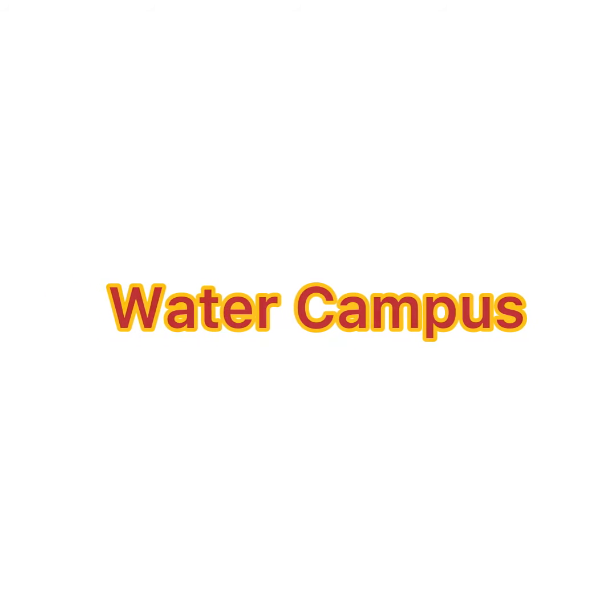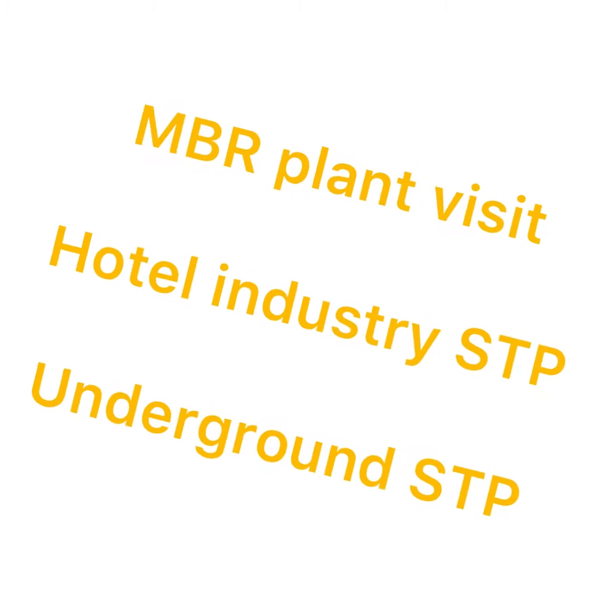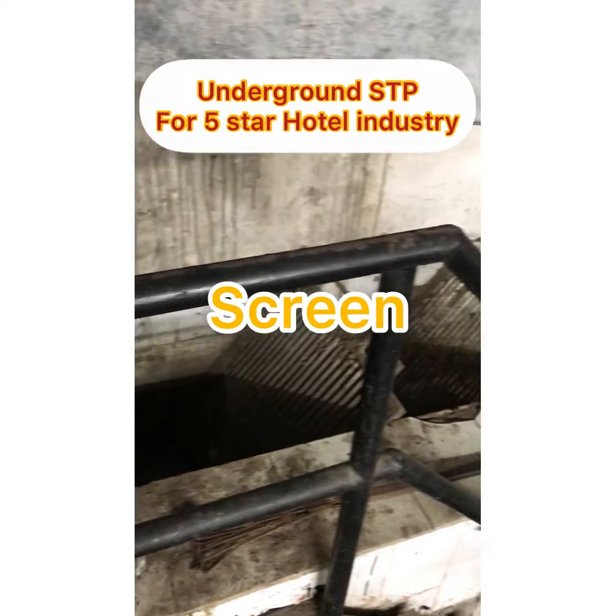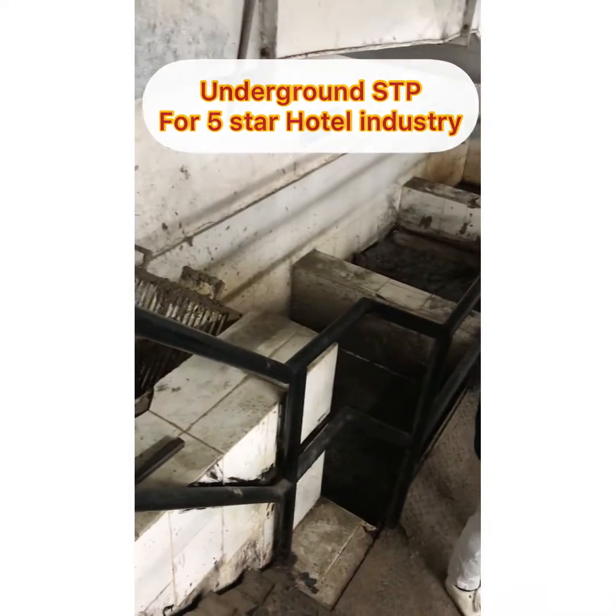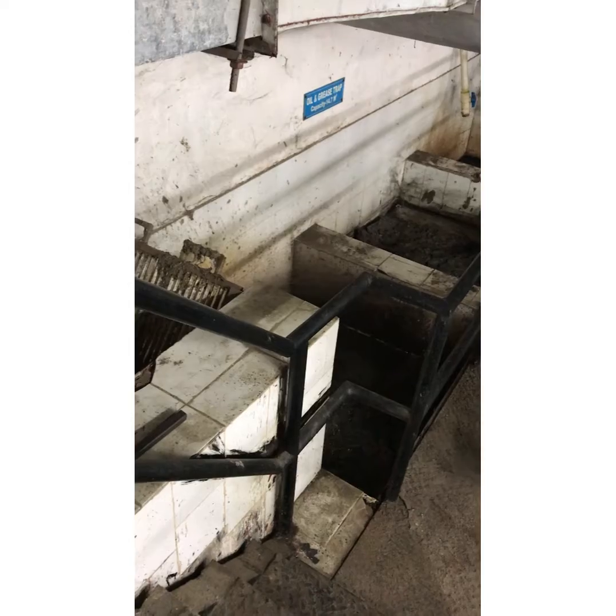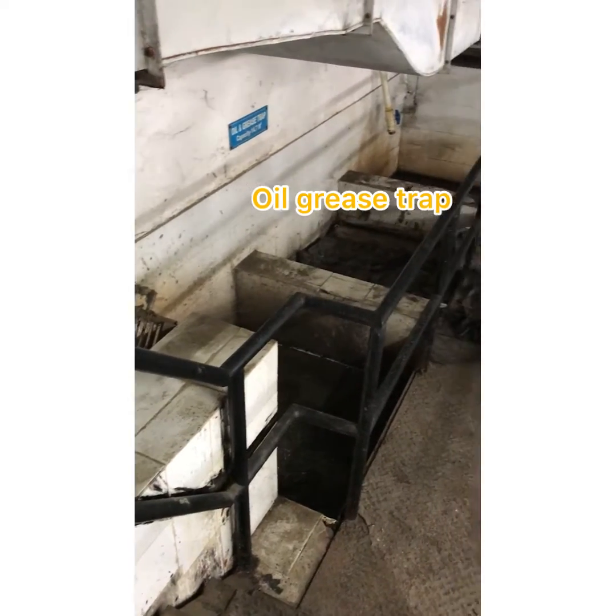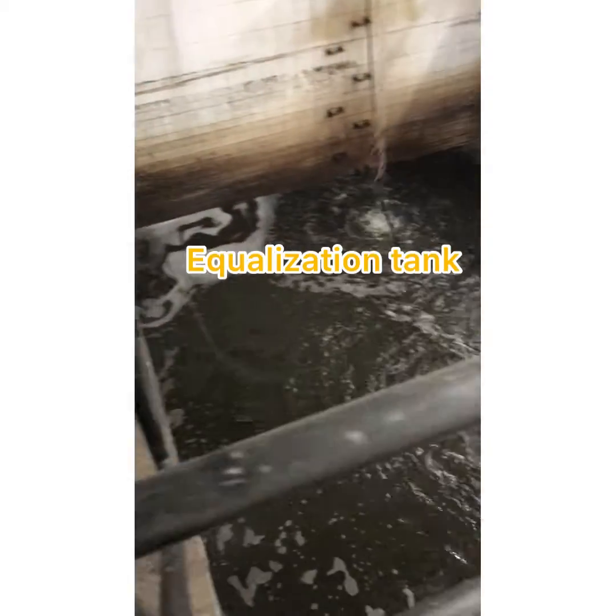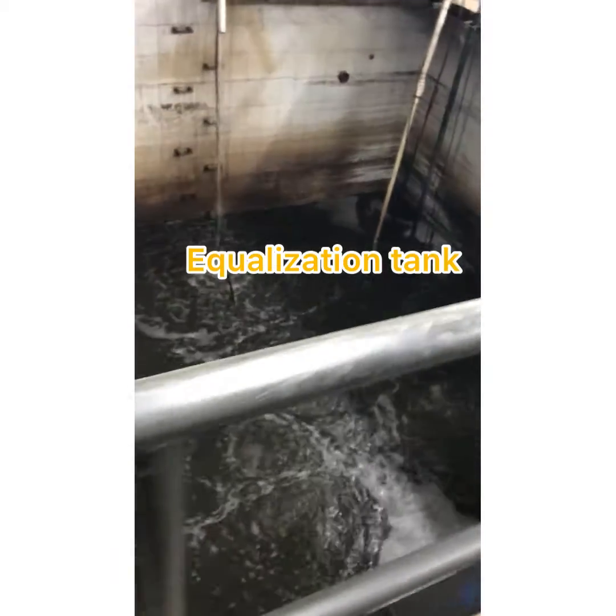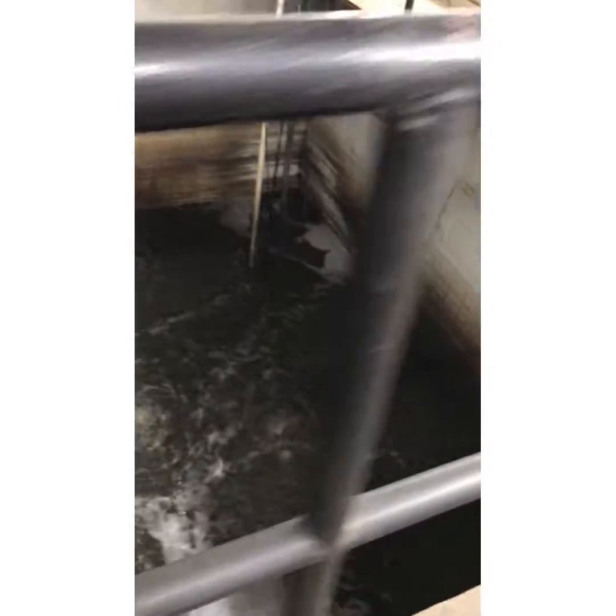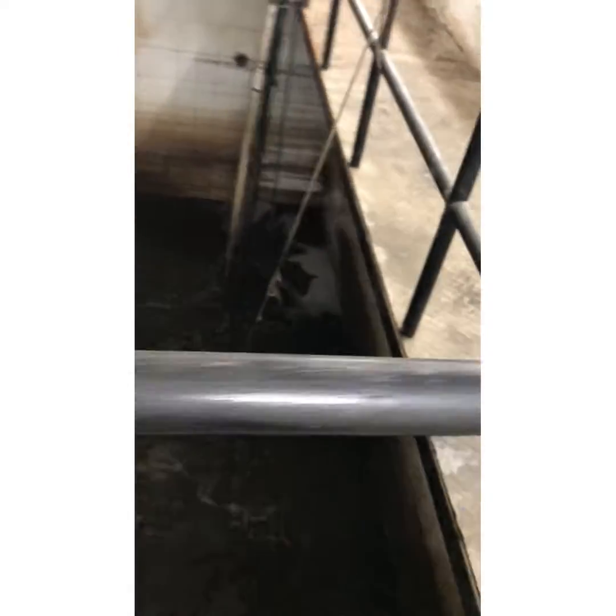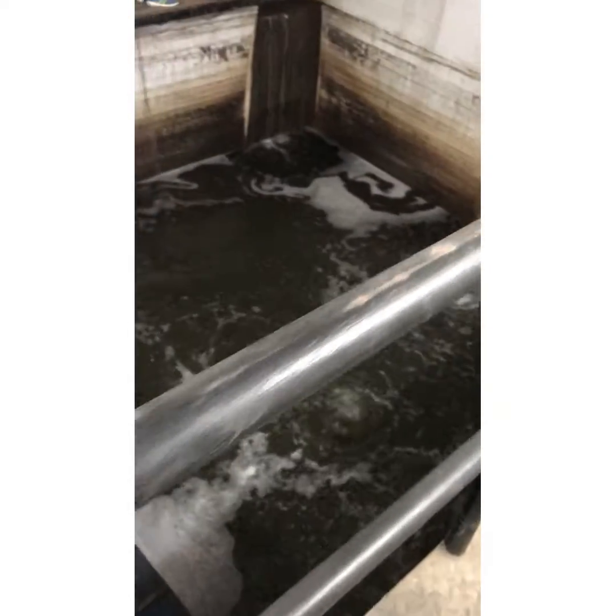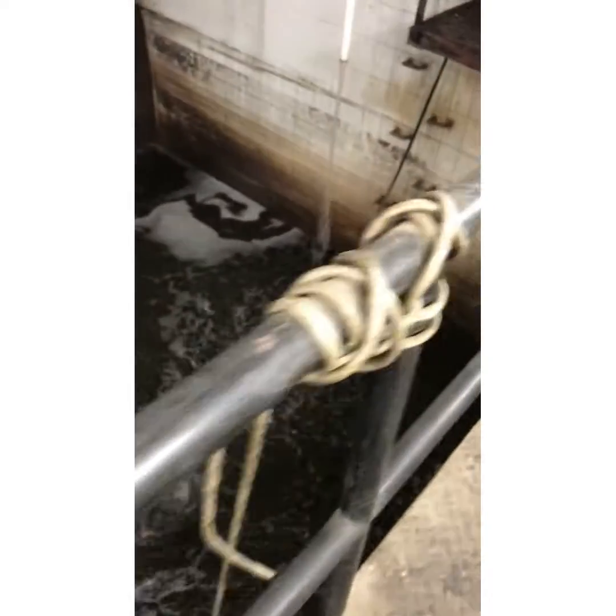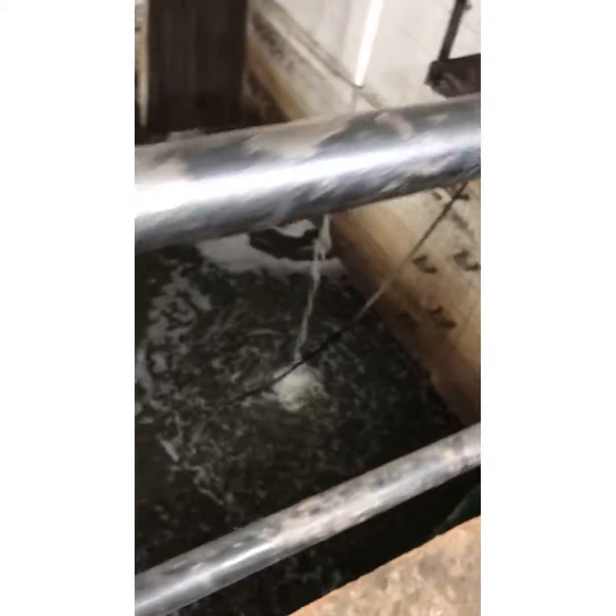Today we will take you to an underground sewage treatment plant, how it works, how it looks and operates. So this is the first unit, the screen. Sewage comes here, all the particles are removed, then an oil and grease trap for removing oil. This is the equalization tank for equalizing the flow and making it uniform, and submersible pumps are there which will transfer the sewage from the equalization tank to another unit.